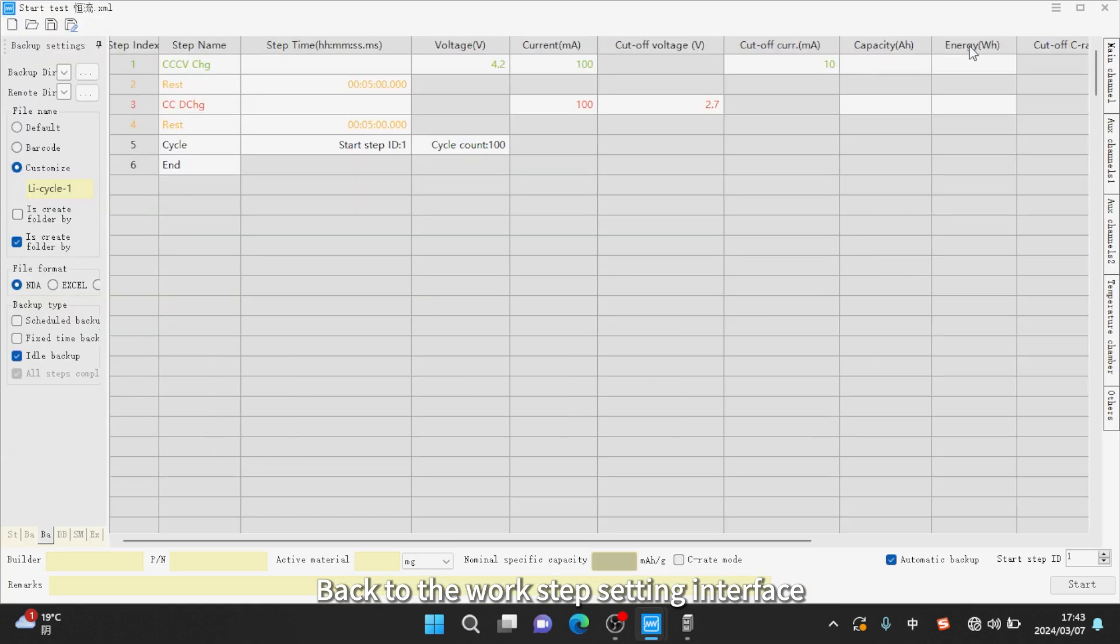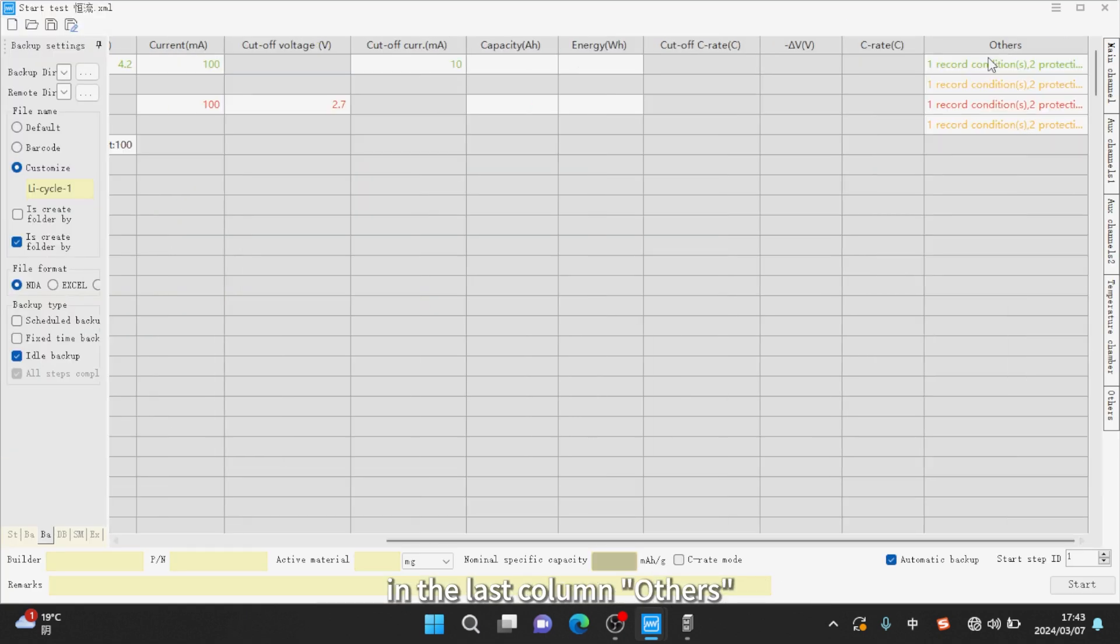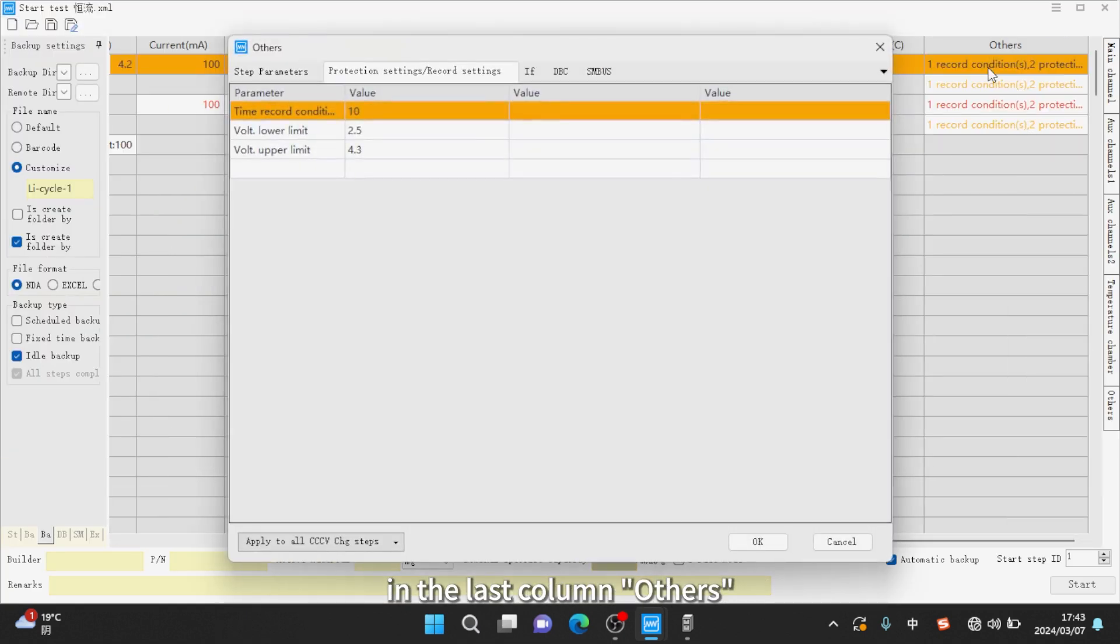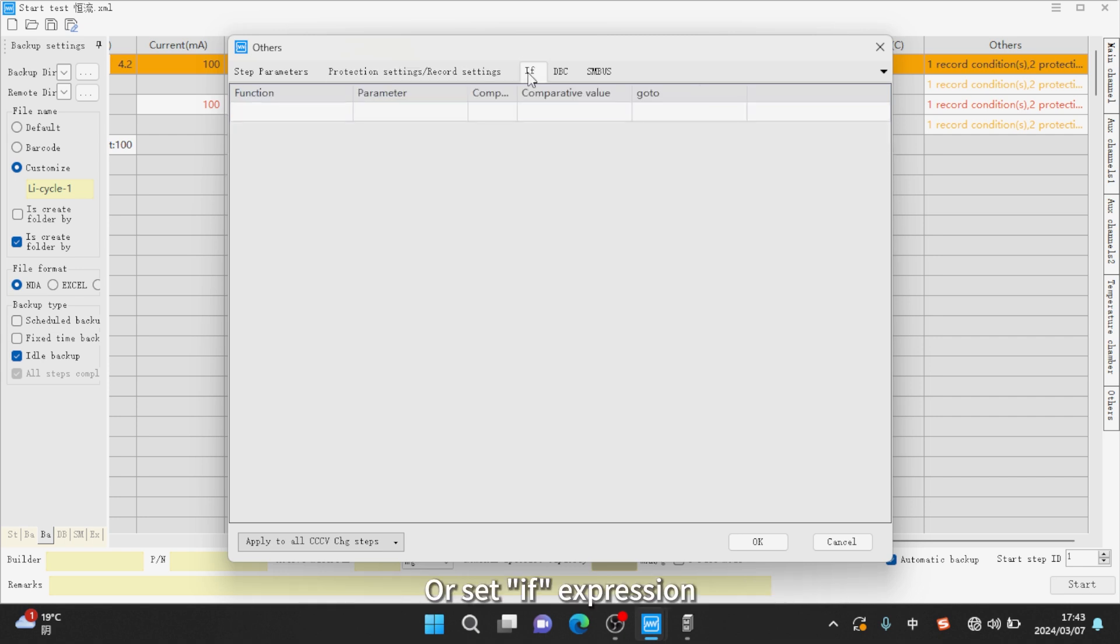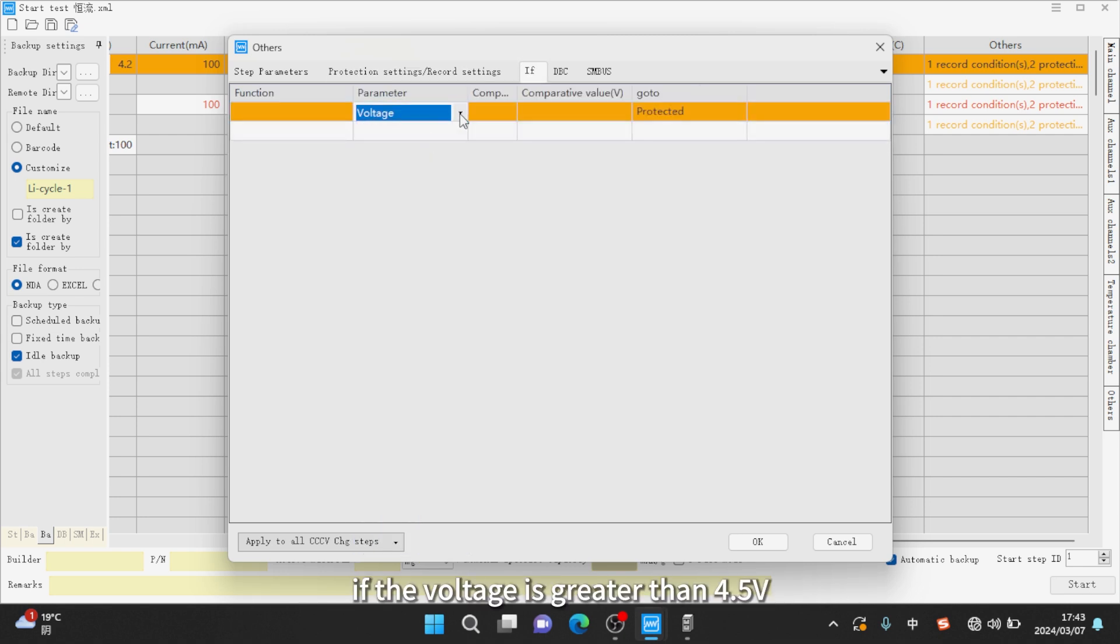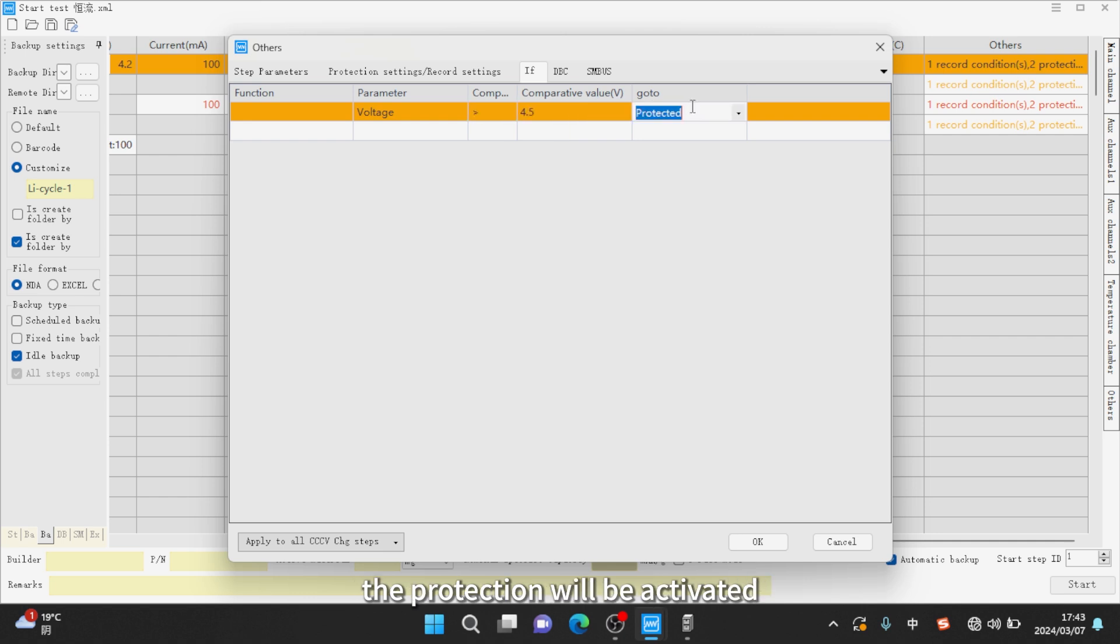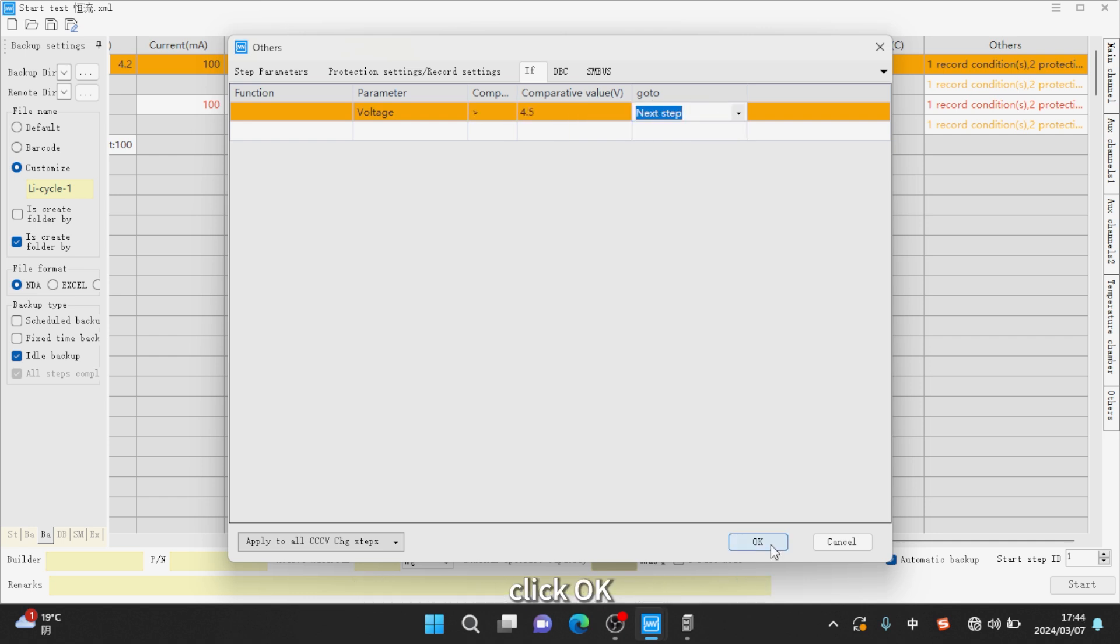Back to the work step setting interface in the last column. Others you can set protection settings slash record settings, or set if expression. For example, if the voltage is greater than 4.5V, the protection will be activated or go to the next step. Click OK.